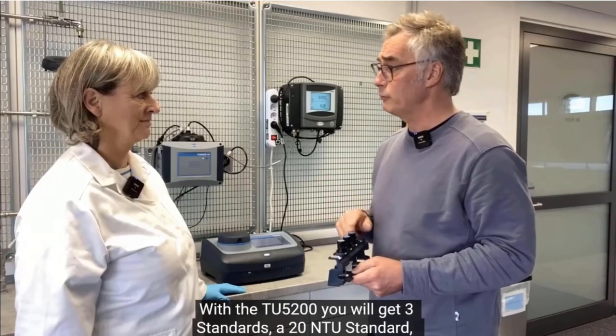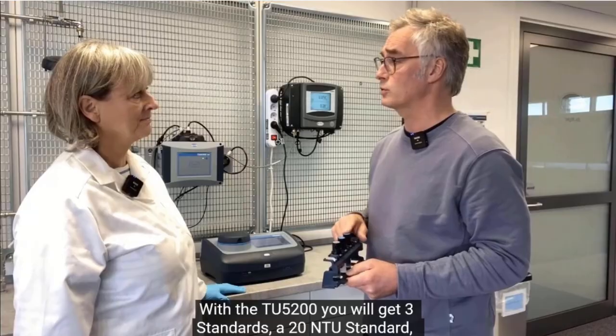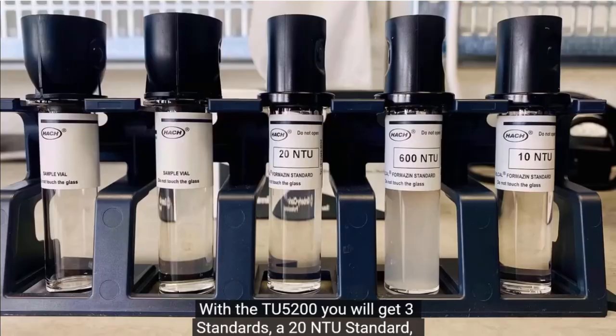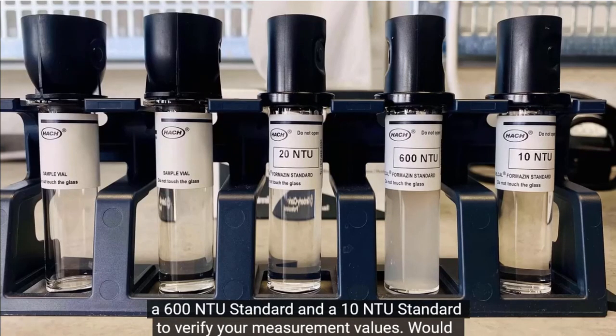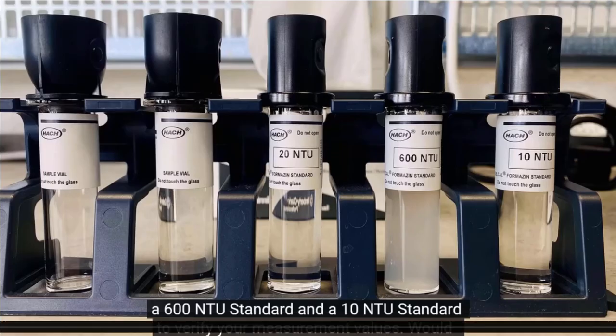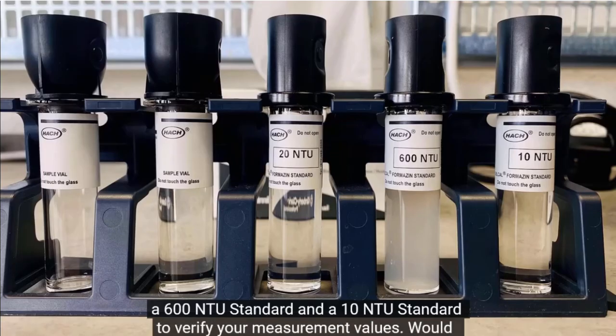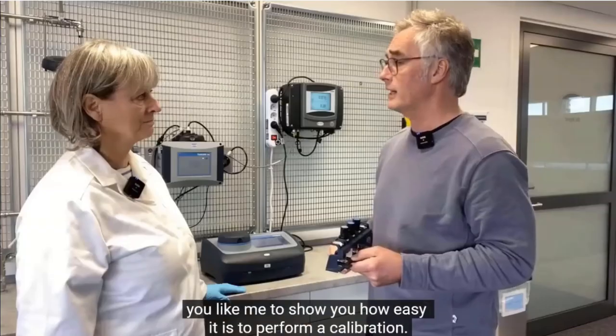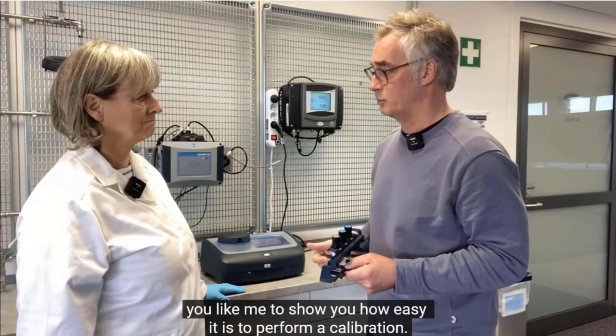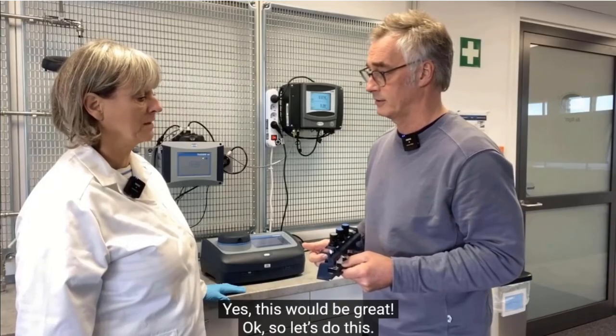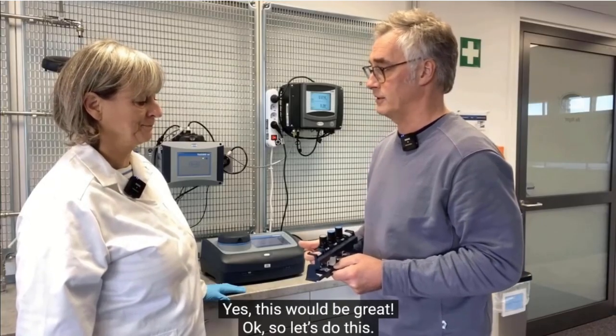Mrs. Kessler, with the TU5200, you also get three standards: a 20 NTU standard, a 600 NTU standard, and a 10 NTU standard to verify your measurement values. Would you like me to show you how easy it is to perform a calibration? Yes, that would be great. Okay, so let's do this.